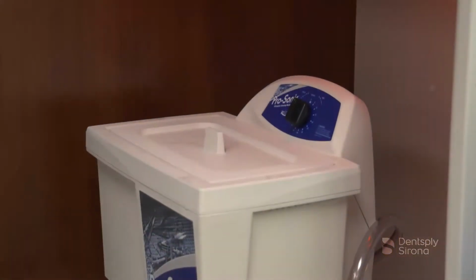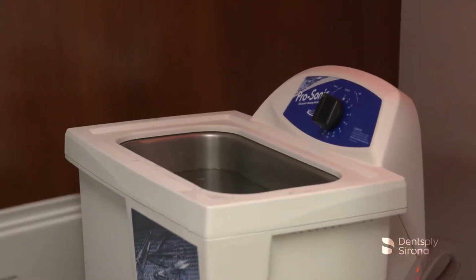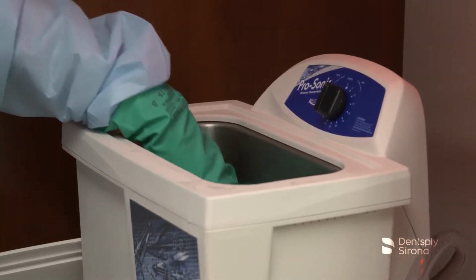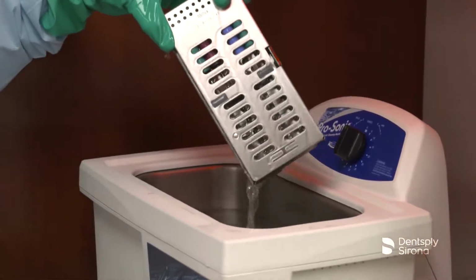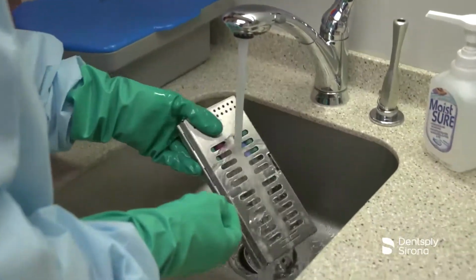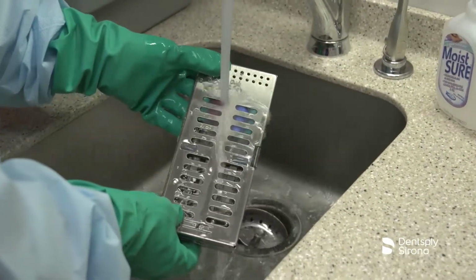After the allotted time in the ultrasonic bath, remove the instruments from the ultrasonic cleaning bath and rinse the inserts under running water for 30 seconds to remove the cleaning agent. A disposable syringe may be used to rinse the holes and cannulas of the Cavitron inserts.